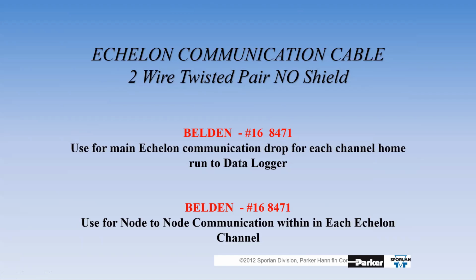I suggest not varying from this, even if the contractor says their company has a cable that's echelon enabled. I've personally been burned by that a couple of times, because it's the capacitance, the impedance, the resistance, how many twists per foot - all of that is in this spec. Any little change in resistance, capacitance, or impedance is going to affect the stability and strength of the network. So please abide by the echelon requirement here.